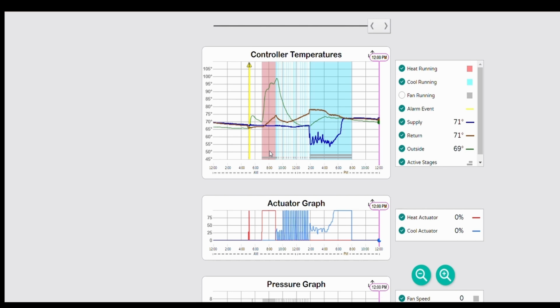I was the one taking over that boiler back in February, and I'm pretty sure on that day, the boiler was not running. So a call for heat, no hot water in the pipes. So even though the actuator was probably 100% open, you had no rise in supply temperature.